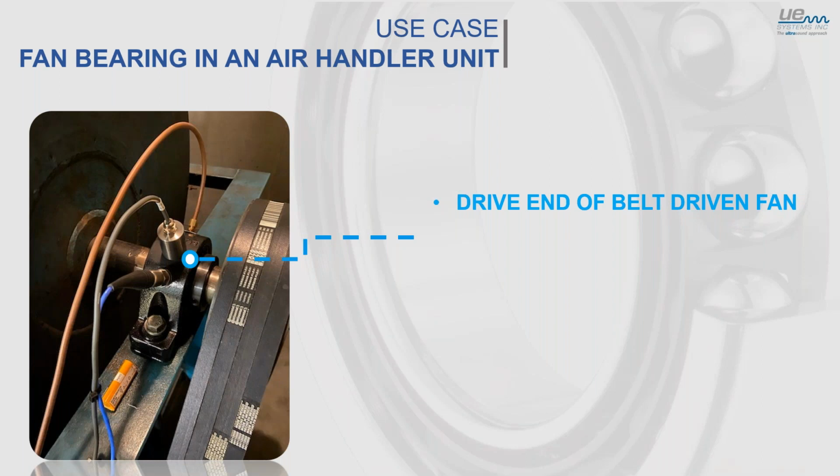So with bringing confidence into these remote systems, we said we can't go out there and keep on adjusting the sensitivity. So what we did with our 850S, some of you might be familiar with our 750 sensor, this is a continuation on that technology, which has been proven for decades. What it allows us to do is automatically adjust the sensitivity for that bearing type, for that bearing speed, in the sensor itself. So we have contributed to the global microchip shortage by putting a whole bunch more into these sensors, but it allows us to bring confidence. And in fact, I'm going to show you a case study which I didn't think was possible, and I told our team not to do it, which was on just over 1 RPM bearing.